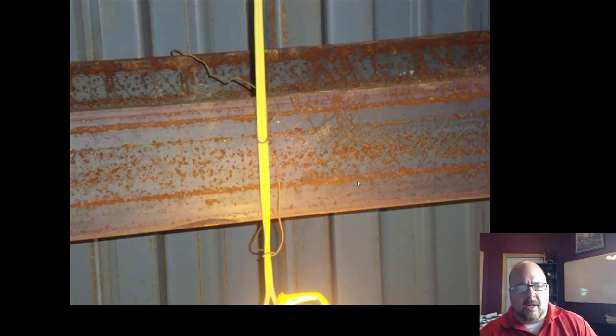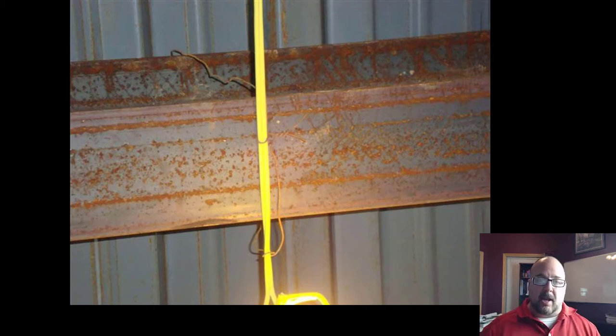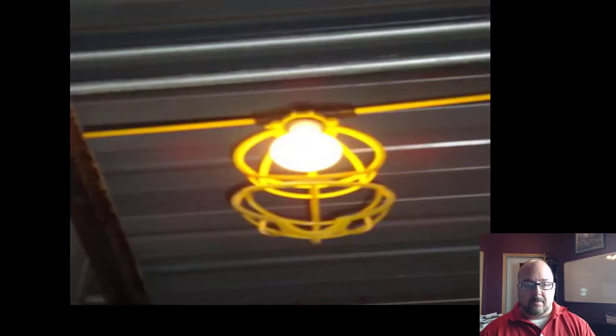Here what Todd is showing us is a line that's being secured to a metal beam by metal. Metal tends to be sharper, especially when it gets kinked, and it can actually cut into the cord. And then if that contacts this metal beam, it would energize the metal beam, so if somebody made contact with it, they could become part of the circuit and get shocked, possibly electrocuted.